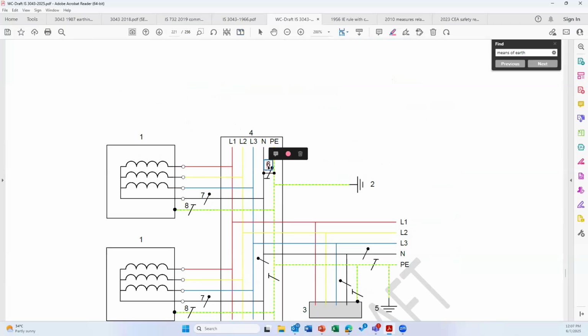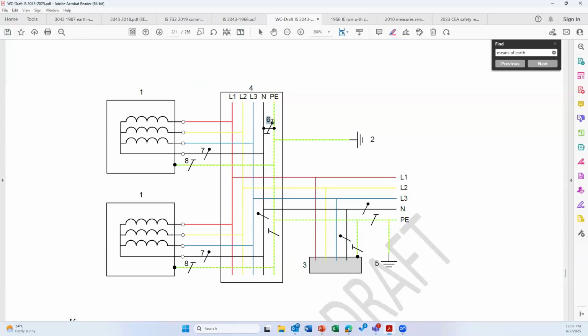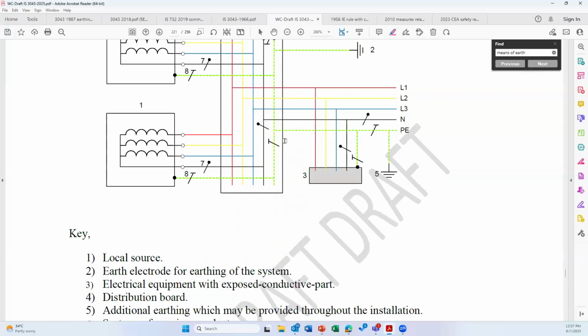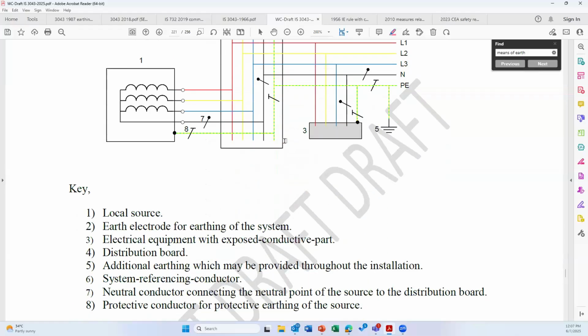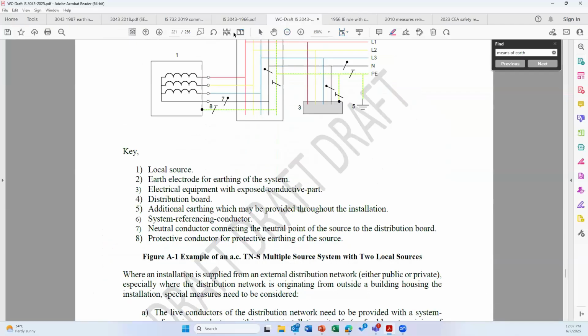The best practice is to make the neutral earthing inside the main distribution board, as you can see here, number 6. So the name of neutral earthing is slowly changing to system referencing, and system referencing means neutral earthing. The best place to make the neutral earthing is inside the main distribution board. Those informations are given here, but it may take some time for the market to learn and do it. But this is the best method.